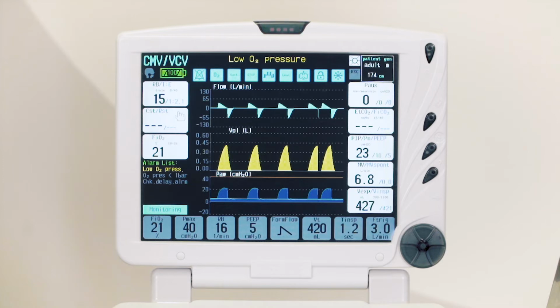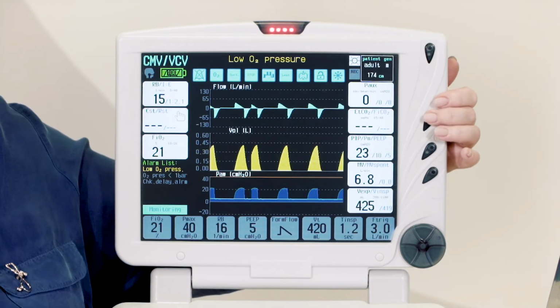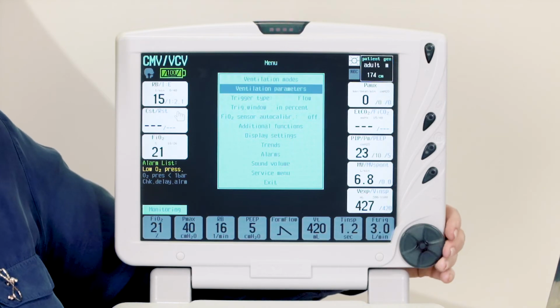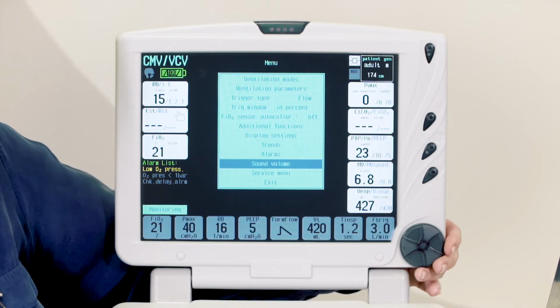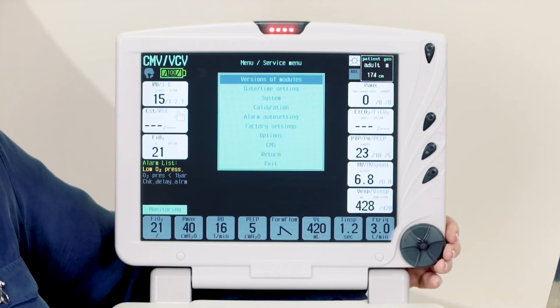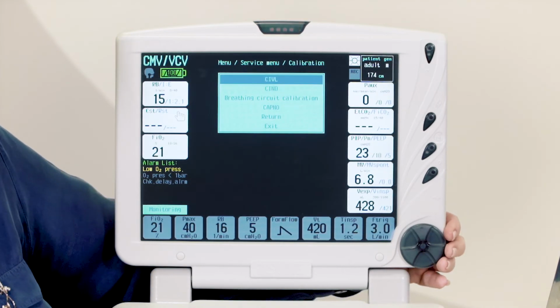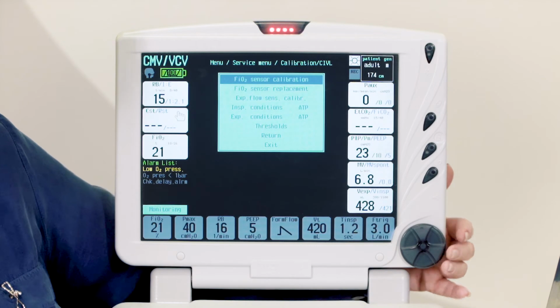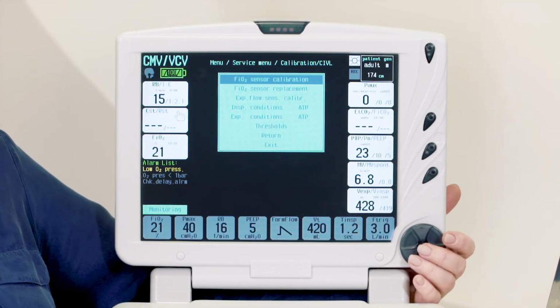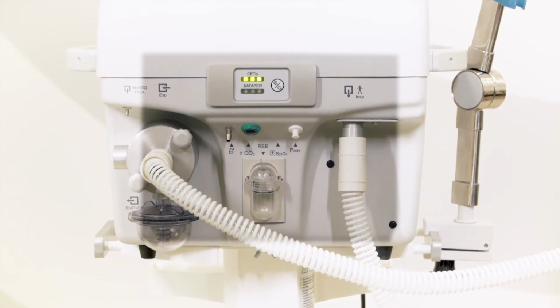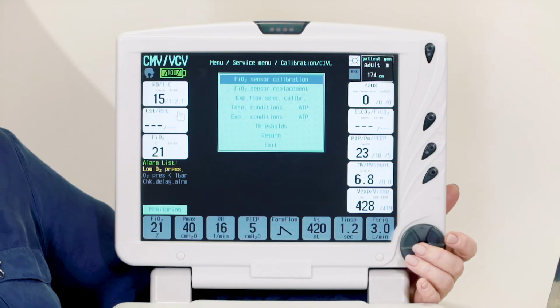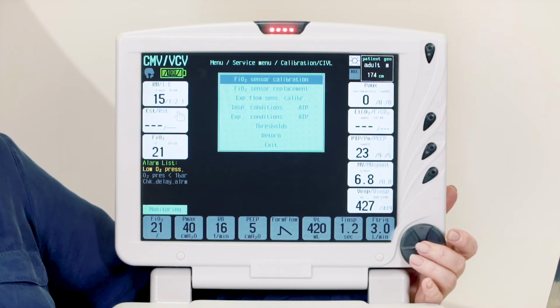For the calibration of the FiO2 sensor, disconnect the device from the patient, press main menu, service menu, calibration, CIVL, FiO2 sensor calibration. Disconnect the breathing circuit. Press the encoder to start the calibration. Sensor calibration takes about 1 minute.